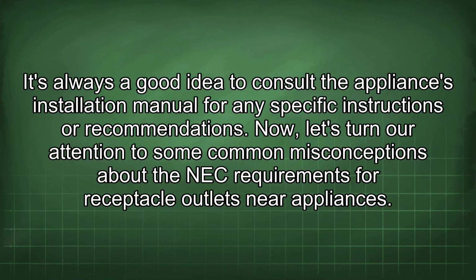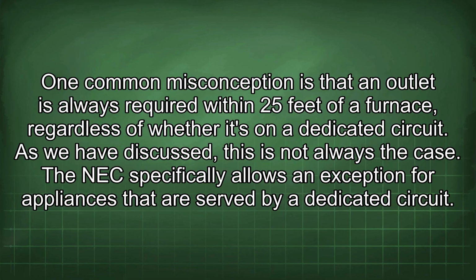Now, let's turn our attention to some common misconceptions about the NEC requirements for receptacle outlets near appliances. One common misconception is that an outlet is always required within 25 feet of a furnace, regardless of whether it's on a dedicated circuit. As we have discussed, this is not always the case. The NEC specifically allows an exception for appliances that are served by a dedicated circuit.